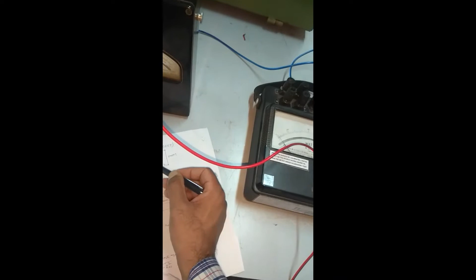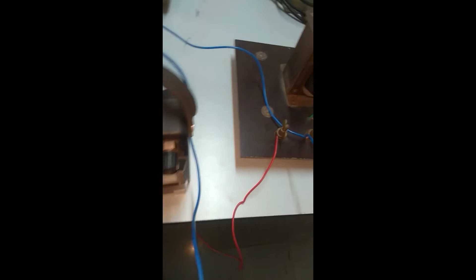In the circuit diagram, we can see that the other terminal of HV is connected to the V terminal of the wattmeter. Here are the voltage terminals of the wattmeter; we need the 150 volt one, so we have connected one wire here, and then it is connected to the other terminal of HV.